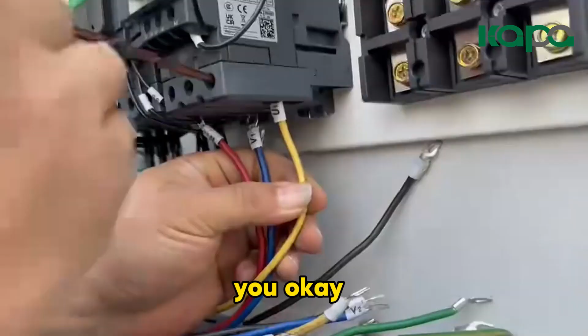Find the UVW line numbers first. Connect the first terminal of the first group. Find the first terminal and look at the main line. This is the first contactor. Find U first, then V and W. We will pull out our 3 lines first. They are respectively connected to the first contactor. The first terminal is connected to U, the second terminal is connected to V, the third terminal connects W. Please be sure to lock it tightly.